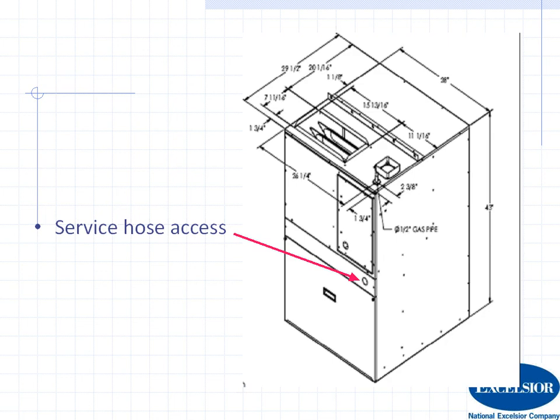good if you have to charge up the unit or do some testing. You wouldn't want to have the main return panel down here off and you bringing in outside air. You wouldn't get your right pressures and temperatures when you're charging up the unit if you had a leak or something like that. So this service access hole is very important. Also, it has a main viewport here on the control panel, which we'll talk a little bit about later on.